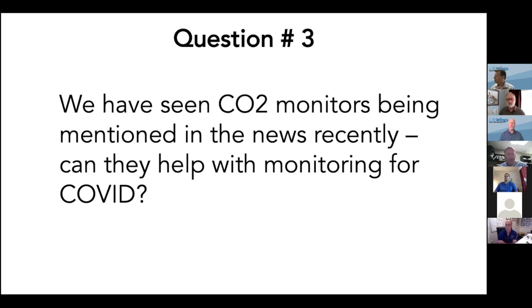CO2 monitoring is best done when the space is occupied. But if it's installed, it really should be tied into your outside air dampers, to open them more if the level goes too high. I've seen a lot of CO2 monitors installed that give you a level but don't do anything with the HVAC system. So it's important that they actually be used for something that can be controlled—that'd be my recommendation.